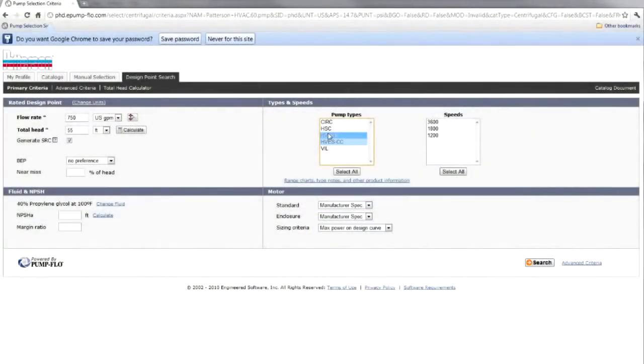But let's say we want to pick this HVES-CC. And actually, I want to look at both, the HVES-CC and the HVES. To select both, you have to hold down the Shift key or the Control key, click on HVES and the HVES-CC. Speeds. What kind of speed do I want? Do I want a high rotating speed? Well, typically that's going to be noisy. Do I want a low rotating speed at 1200? Well, that's going to take the cost of our motors up. So I'm going to try to keep it at 1800 RPM, so I'm going to select 1800 RPM and leave it at that.